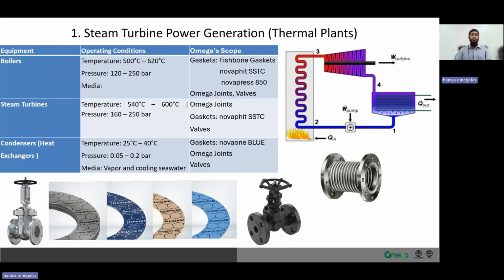Now, if we take a look at the kind of products that go into such an application, for these operating conditions we have gaskets like Novaphit SSTC, we have Nova Press 850, we have Omega joints, and valves for the boilers themselves. Now talking about the steam turbines. Here we have Omega joints, which are the expansion joints, which are very vital for the steam turbines so as to compensate for the vibrations in the system, as well as for the pressure spikes that occur throughout the system. The expansion joints are very important here.